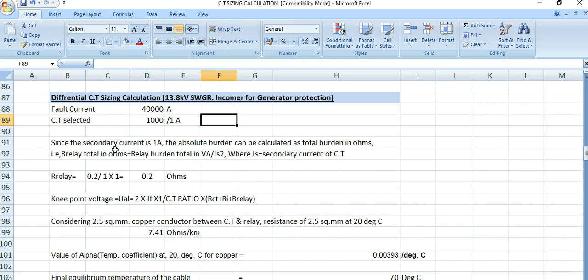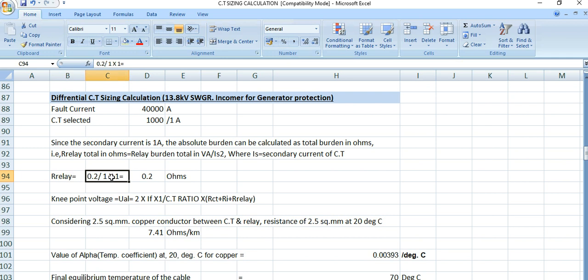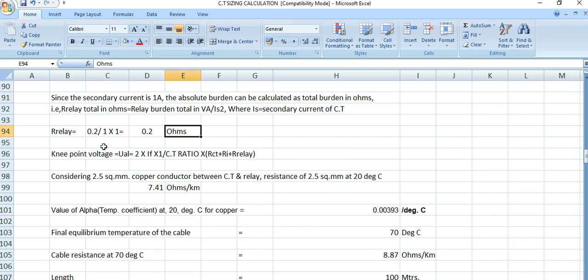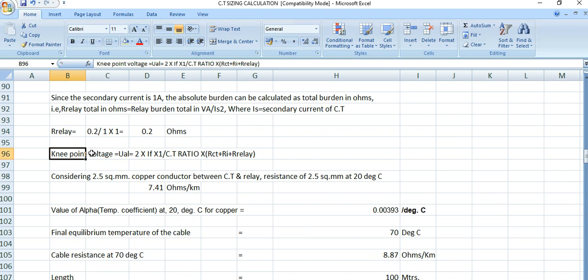Now let's start the lead resistance calculation. The secondary side is 1 ampere, so we can express the burden in ohms. The relay resistance is 0.2 ohms — this is simply the relay resistance which we need to sum up at the end. Now coming to the knee point voltage.